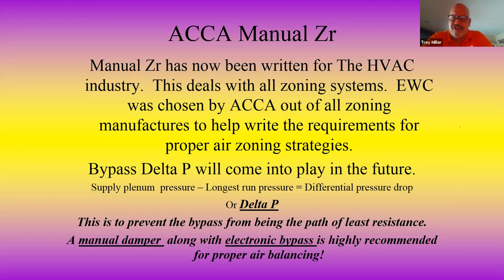One, the bypass is the first takeoff. It's predominantly the shortest takeoff, and it's one of the largest takeoffs. Air's just like water, it's dumb, it takes the path of least resistance. So all the air wants to go down our bypass. We don't want that. We want the air to go down the duct system.